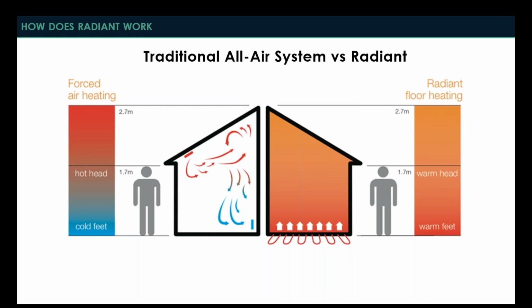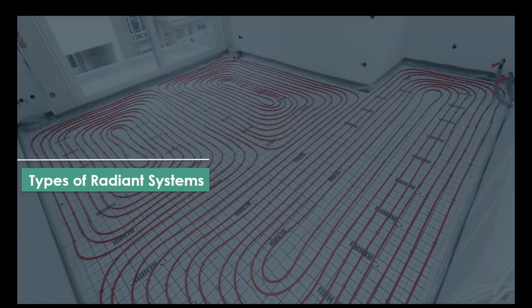Radiant is a little bit different in that it's not relying on convection. It's not relying as much on air temperature in the space, and it's really relying on that direct radiant energy transfer from the occupant to the radiant surface.